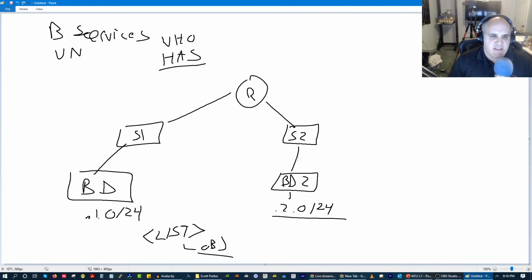Now, the BBMD is the BACnet Broadcast Management Device, and it has a BACnet broadcast definition table or distribution table. I don't remember off the top of my head here. But each BBMD exists on a subnet, and it has a BDT of all BACnet networks.